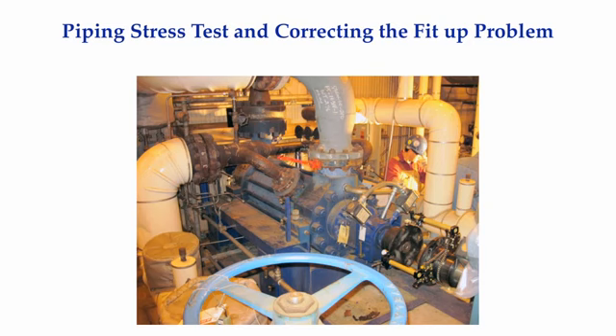We then removed the suction flange bolts and removed the suction pipe, and the pump moved sideways about 6 mils. We then loosened the outboard foot bolts, and the pump moved further upwards 80 mils and sideways about 30 mils. At this point, only the discharge pipe was attached. We then loosened the discharge flange bolts, and the pump dropped back down and set on the base plate.